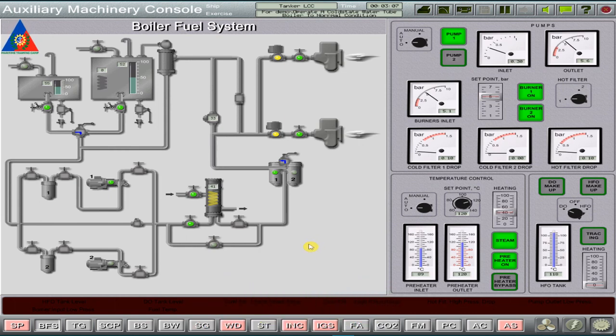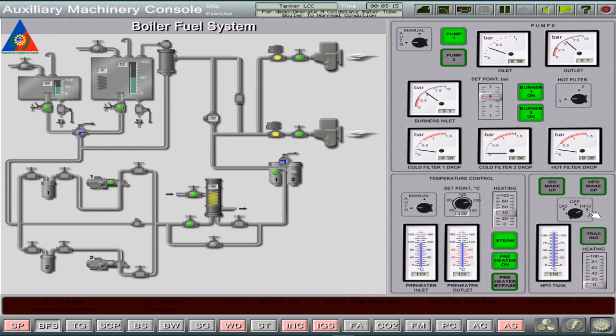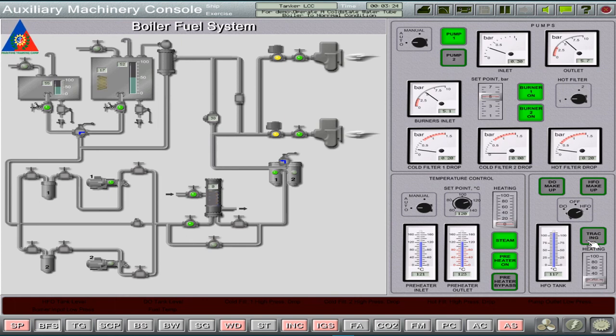Now, let's change over the selector switch to heavy fuel oil burner consumption, then open 10% the heating to the heavy fuel oil tank, including the tracing steam lines to maintain good fuel viscosity to the burners.